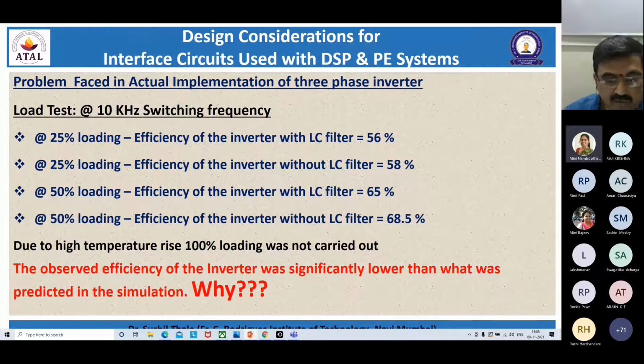We thought the LC filter might be causing trouble, so we removed it and took the output directly from the inverter module. There we found an efficiency improvement of 2% at 25% loading. Similarly at 50% loading, we got 65% efficiency as against 68.5% without the LC filter. We also witnessed a very high temperature rise at 100% loading, so 100% loading was not carried out.